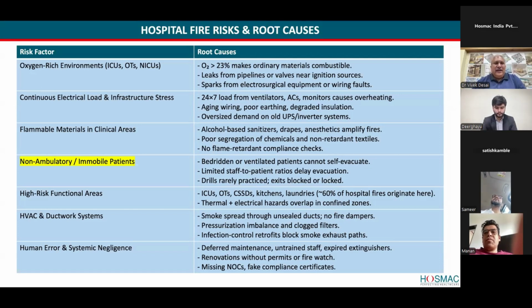Then HVAC and ductwork systems, so the other problem, which we will talk about with Satish also, and he will explain more about it, is that smoke spreads through unsealed ducts. And if there are no fire dampers, if there is a pressurization imbalance, or the filters are clogged, all of these kinds of things lead to the spread of fire. Satish, would you like to talk about this a little bit, what one should do to avoid this?